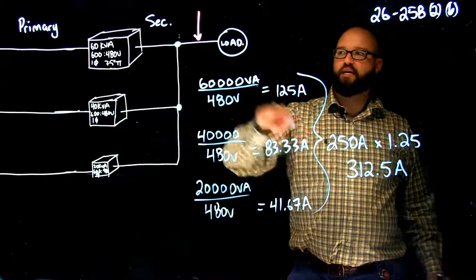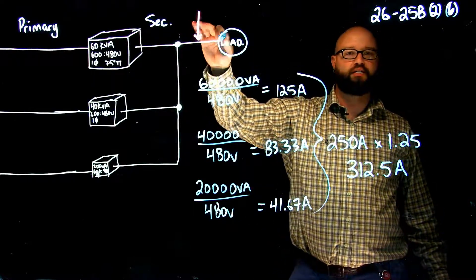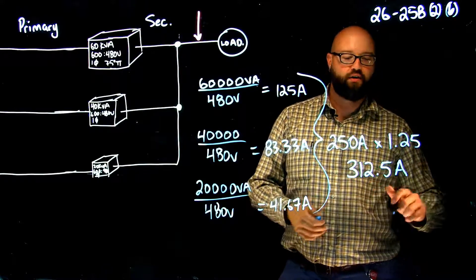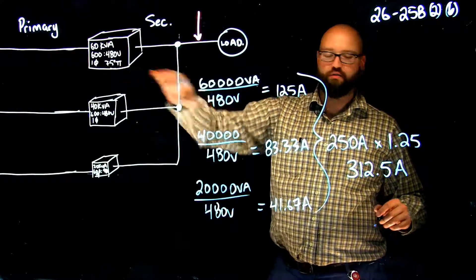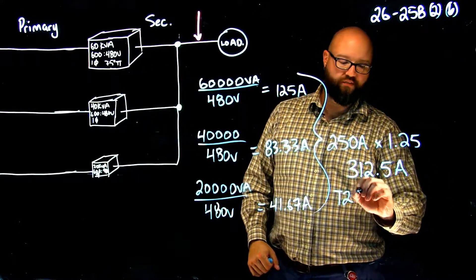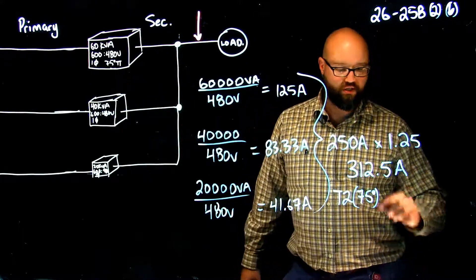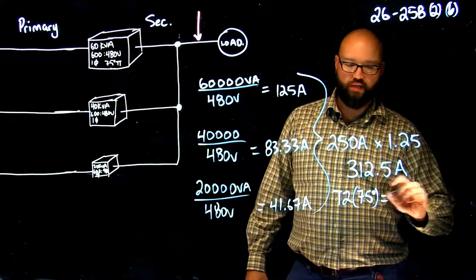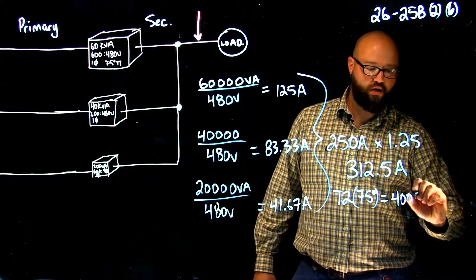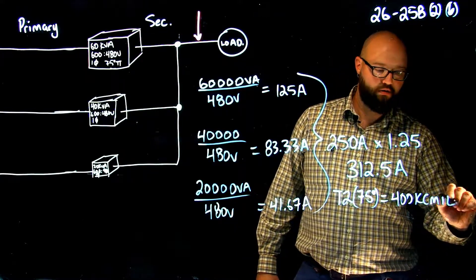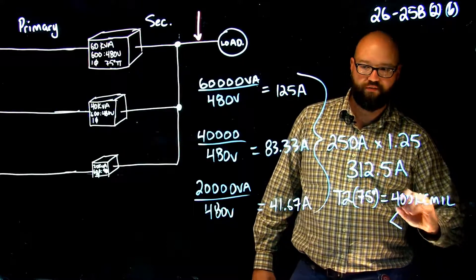That is the minimum size that this conductor right here can be, that's the minimum ampacity of this conductor. Again we're going to take this to table 2, 75 degree column, because I'm given this 75 degree termination, and we are going to choose a 400 kcmil with an ampacity of 335 amps.